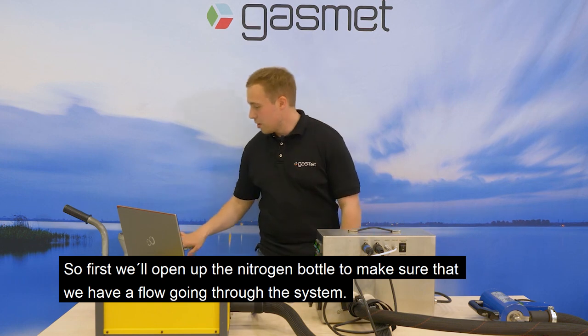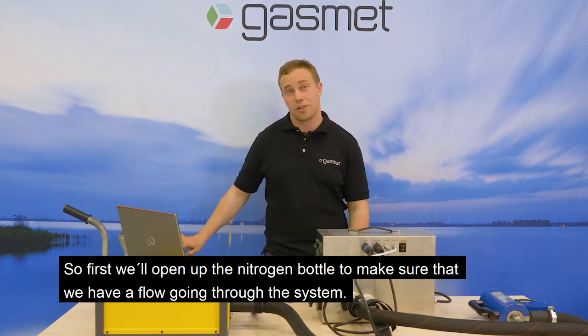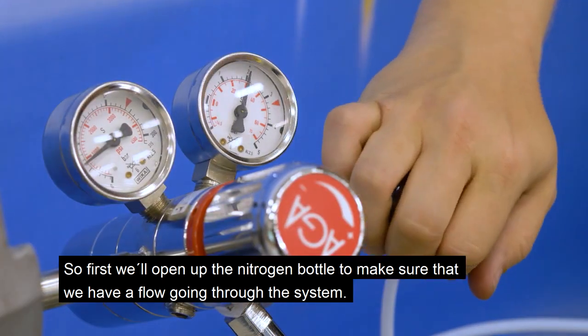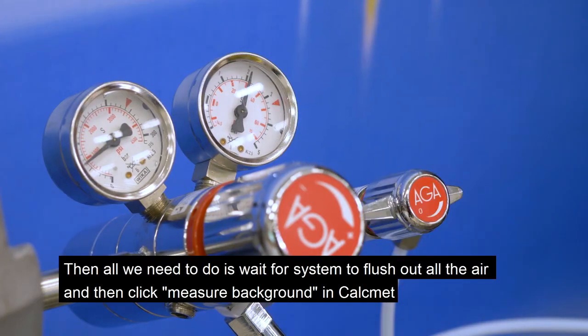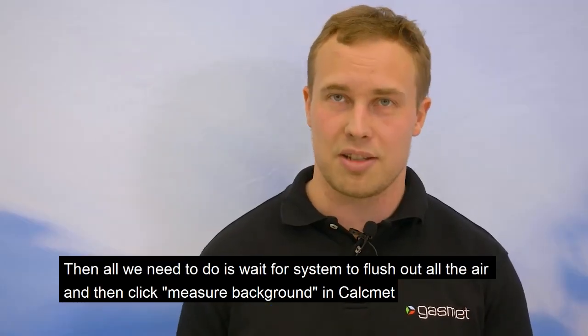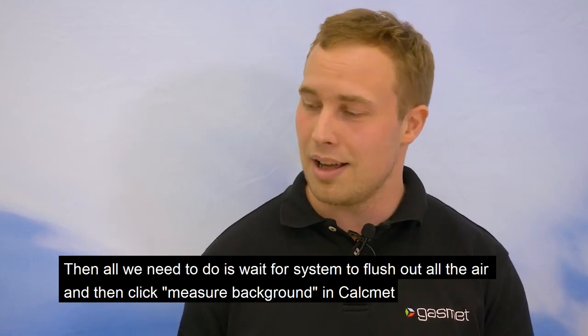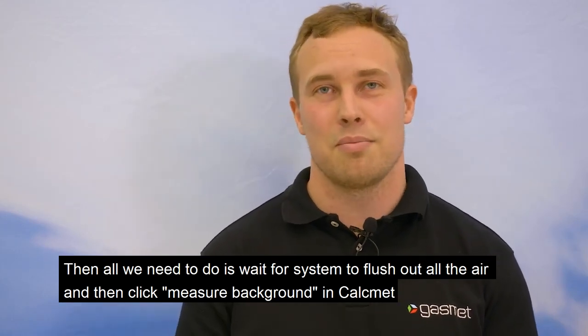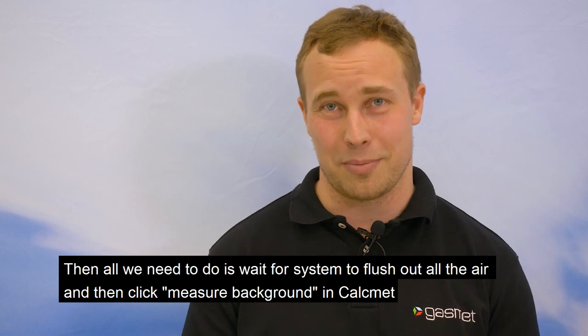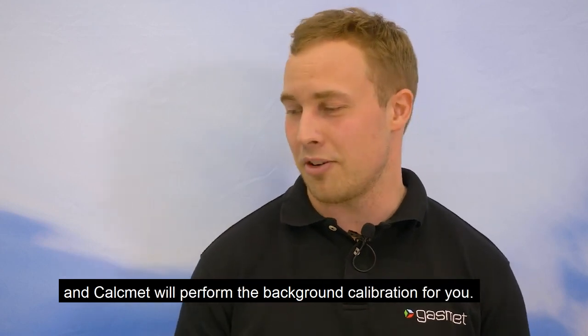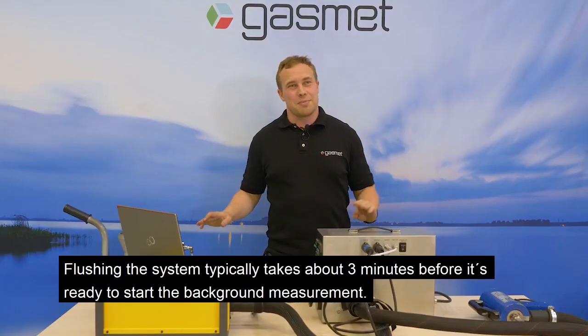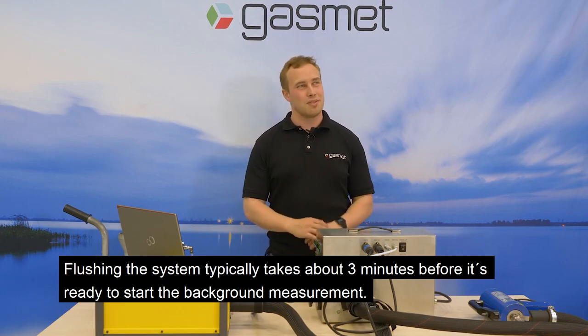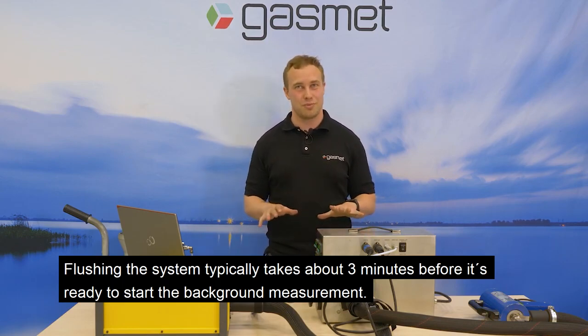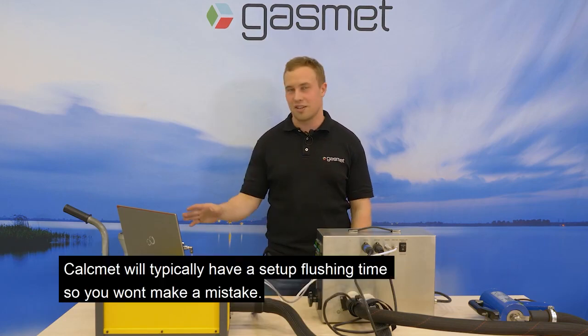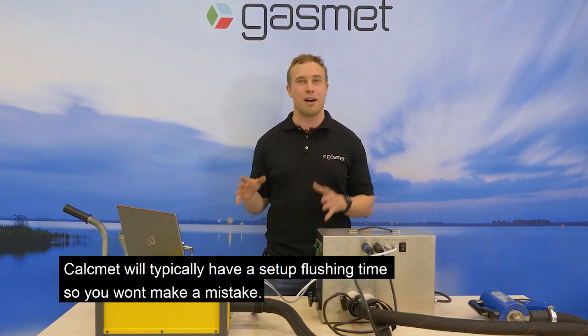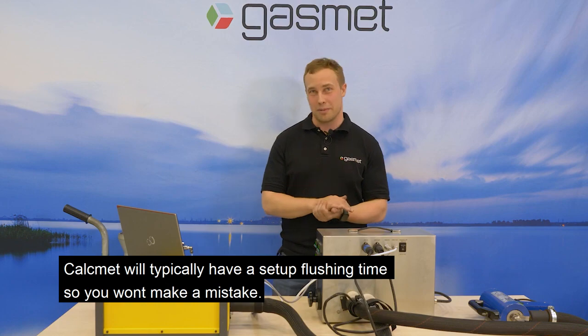So first we will open up the nitrogen bottle to make sure that we have a flow going through the system. And then all we need to do is wait for the system to flush out all the air and then click measure background in Calcmet, and Calcmet will perform the background calibration for you. Flushing the system typically takes about 3 minutes before it's ready to start the background measurement. Calcmet will typically have set up a flushing time so that you won't make a mistake.